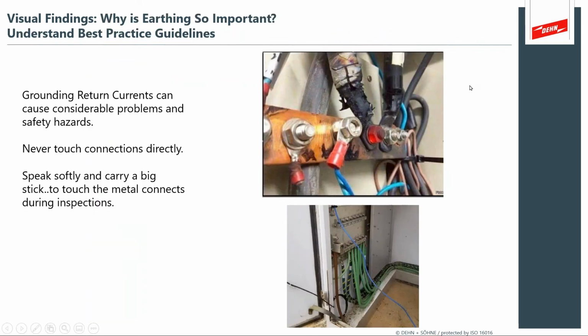So, visual findings. Why is earthing so important? Well, you can see in this photograph above that there's a grounding return current that is so high that it causes considerable safety hazard. And what's happening right here in that conductor is that so much ground current is flowing that it's causing the fastener to glow cherry hot. That's extreme safety hazard. And it's a lesson to provide the inspector experience that you don't just go in and start touching some of these apparatus. Never touch those connections directly. Speak softly and carry a wooden stick, because you don't want to be the one that's touching that stuff directly.